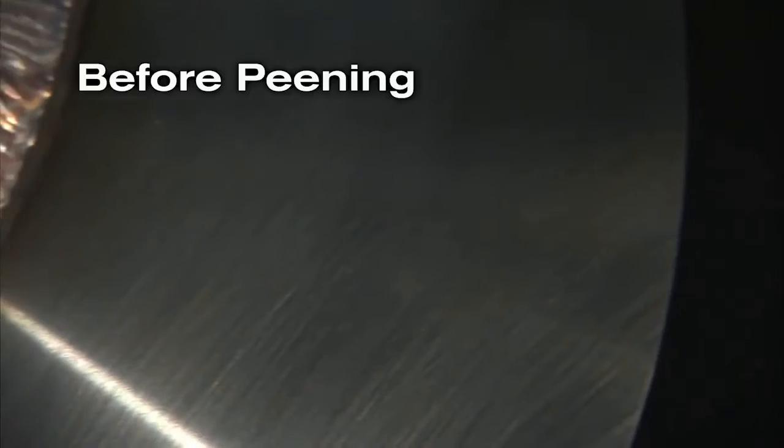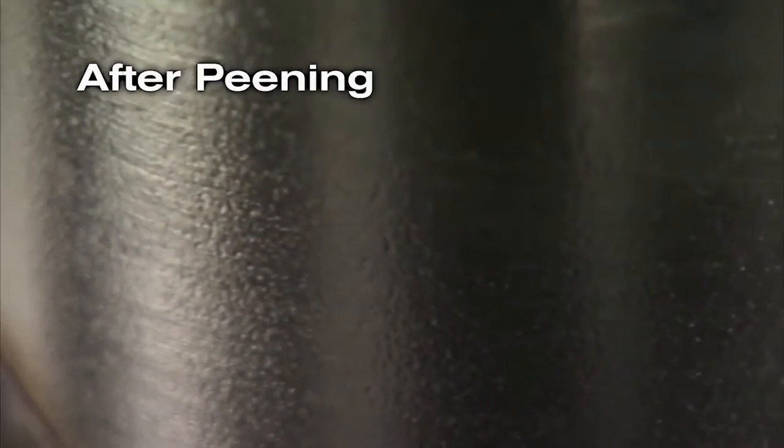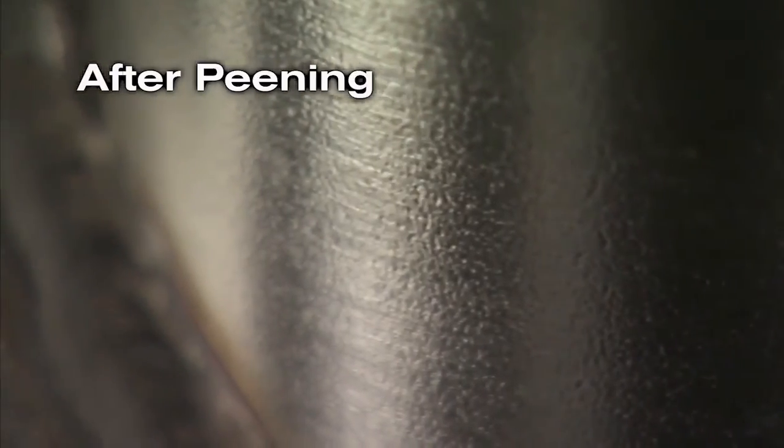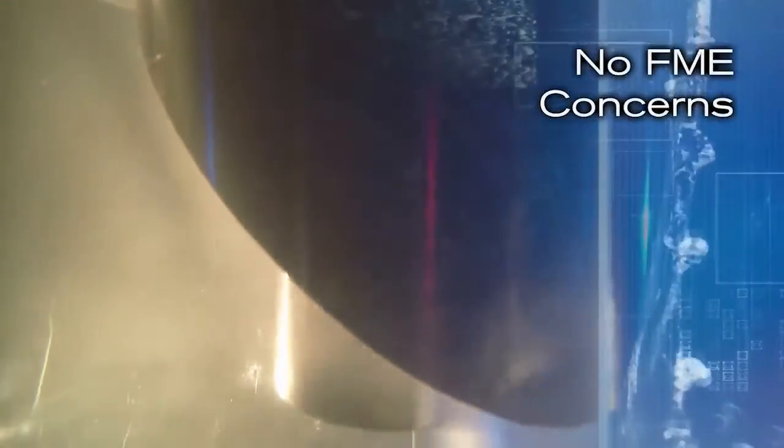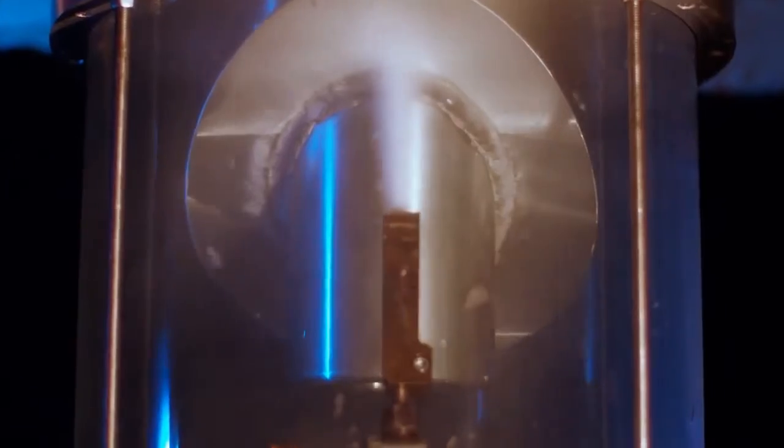Cavitation peening technology is proven and has been safely used for nuclear power plants in Japan. Since no material is being removed, there's minimal risk to system components. The process uses water and absolutely no debris is produced. The process is available in the U.S. for use on reactor vessel head nozzles, reactor vessel nozzles, and bottom mounted nozzles.